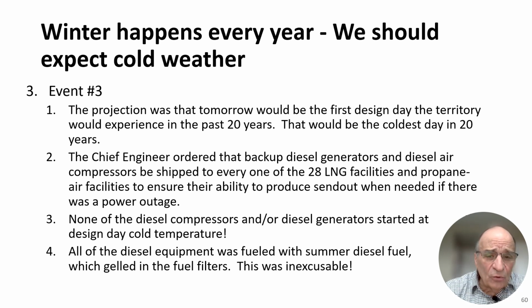The chief engineer ordered that backup diesel generators and diesel air compressors be shipped to every one of the 28 LNG facilities and propane air facilities to ensure their ability to produce send-out when needed if there was a power outage. None of the diesel generators or compressors started on that design day. Not a one. All of the diesel equipment was fueled with summer diesel fuel, which gelled up in the fuel filters. This was inexcusable.